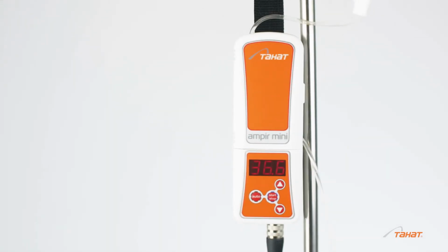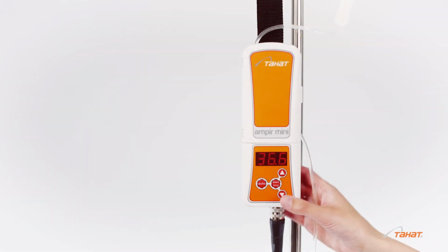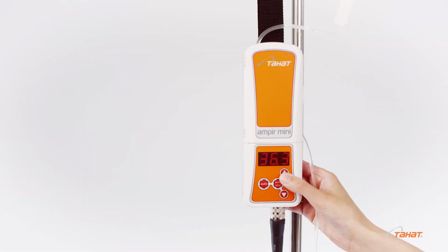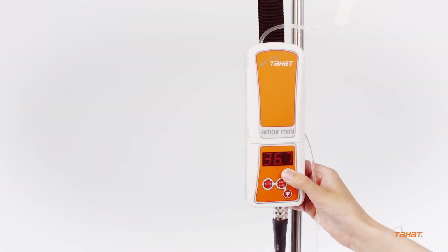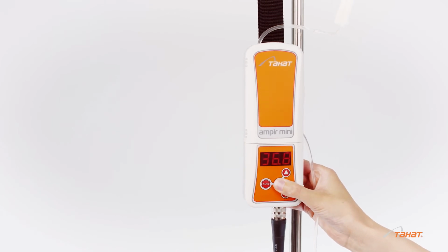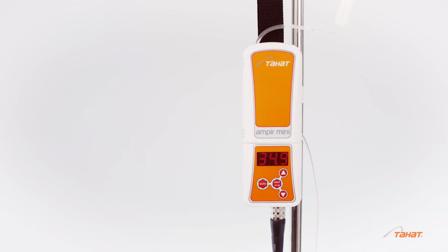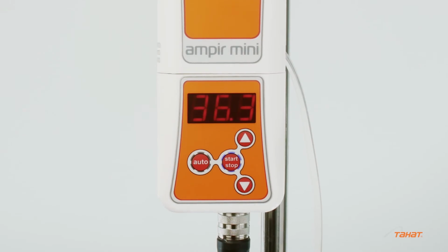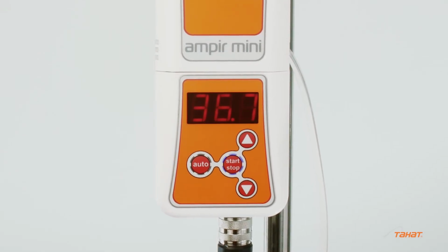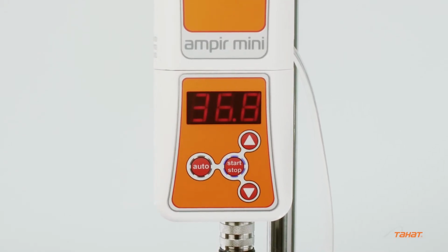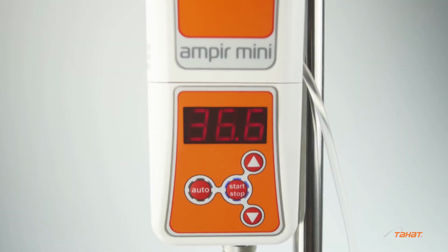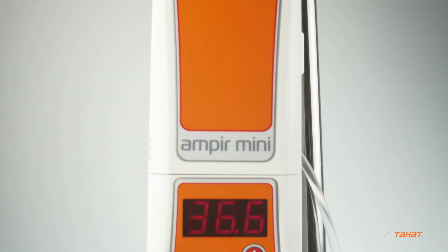Previously set temperature will appear on the display. Select the warming mode, manual or auto. Working in manual mode, set the required temperature and press the start button. Manual mode allows you to set the temperature in the range of 34 to 42 degrees Celsius. Current temperature of the heat exchanger will be displayed.